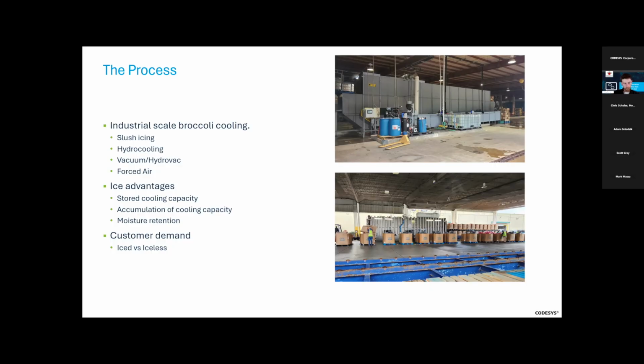Hydrocooling is another common method, and a lot of iceless broccoli is done this way. This machine up here is a hydrocooling tunnel. With a hydrocooling process, we have tanks or plate chillers that cool the water with a lot of mechanical refrigeration to near freezing, 32, 34 degrees, and we just pour it over top of the product. This has a big chain in it that moves the product through in 20, 30 minutes. Sometimes they're a batch system where you just set them in and cool them, but this is a continuous process style. A thing to note with hydrocooling is that we'll sometimes combine it with slush icing to get the best of both worlds.